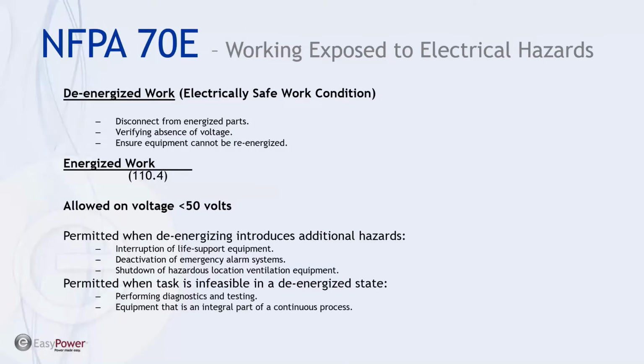So NFPA 70E, as I say, directs that de-energized work is the only safe work condition, but they give us three categories in which electrical work can be done while the equipment's energized. First is when the voltage on the equipment is less than 50 volts. So this is how telecom equipment can be operated and debugged and worked on without de-energization.